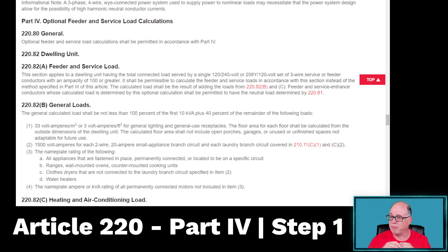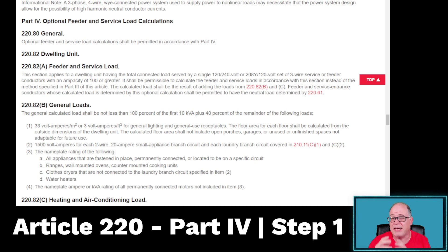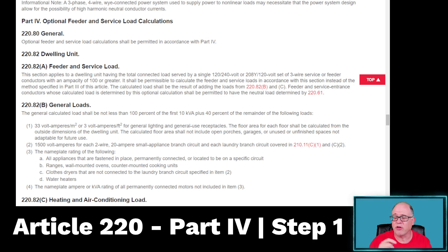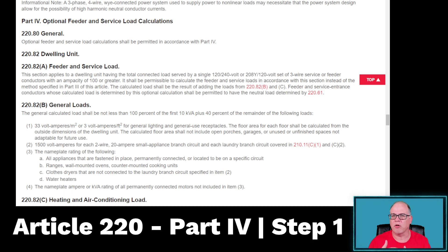The ampacity has to be 100 amps or greater, and you can use this method for sizing the service or the feeder instead of using Part 3. How you're going to do this is apply all of the things in 220.82B, and then all of the things in 220.82C. For items in B, you're going to be able to apply demand factors: the first 10,000 at 100% and the remaining at 40%. When it comes to 220.82C, you just choose which is larger — the AC or the heat — and run with it. It's much simpler to do the optional method than the standard method.